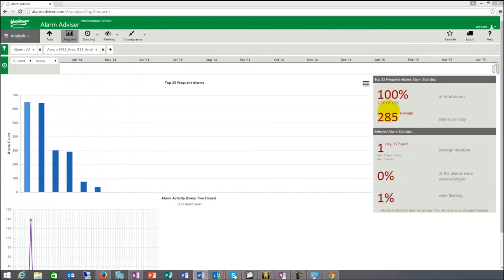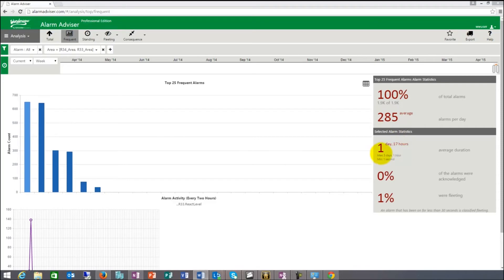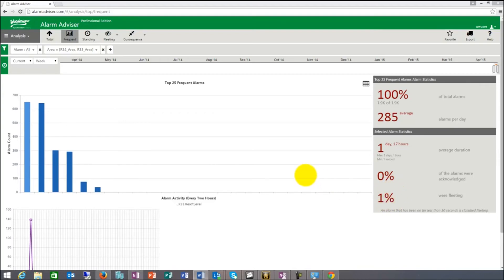Those key metrics are presented in these widgets. These widgets actually say, okay, for the current week, you have 1900 alarms, 285 alarms a day. And then the selected alarm statistics here are 1 day and 17 hours. And 1% were fleeting and 0% of the alarms were acknowledged. Basically none of the alarms were acknowledged in this case.